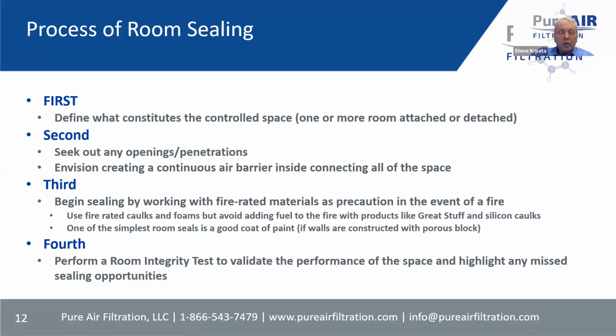Masonry blocks have cells, and if you were to pour water in, eventually you'd see it leaching out because it's porous. So if you have a room made of block, one of the first things you'd want to do is paint it to seal it. It's one of the simplest, cheapest ways of sealing a room. Depending on the atmosphere outside the room, contaminants would otherwise filter through the pores in the blocks and into the space. We're not painters ourselves, but getting a painter to put a good coat of paint on that block goes a long way toward improving the room.